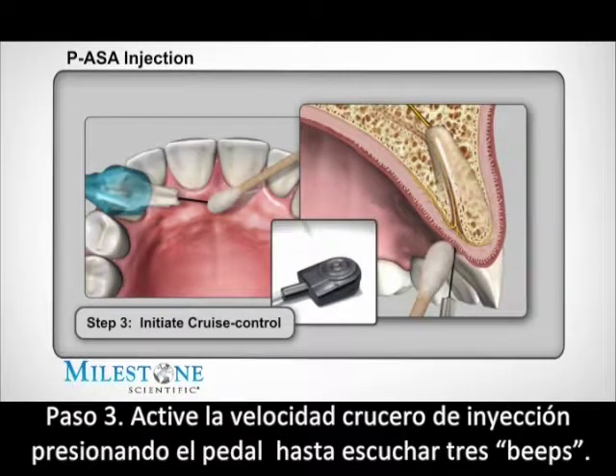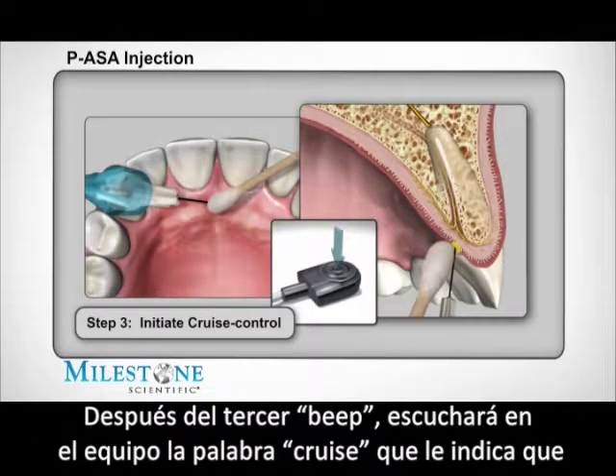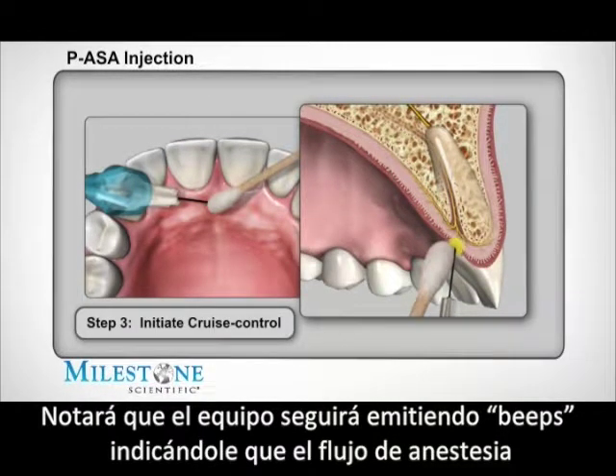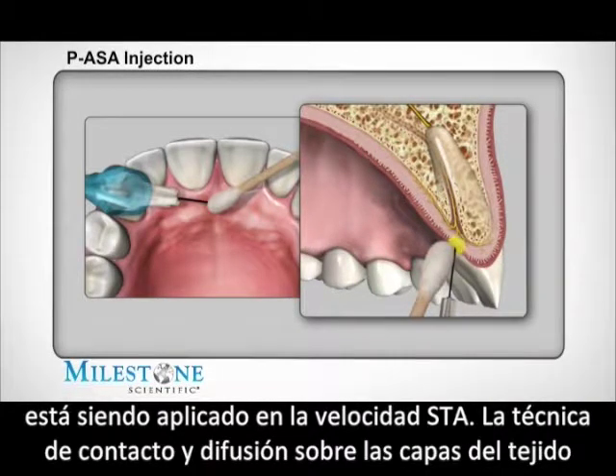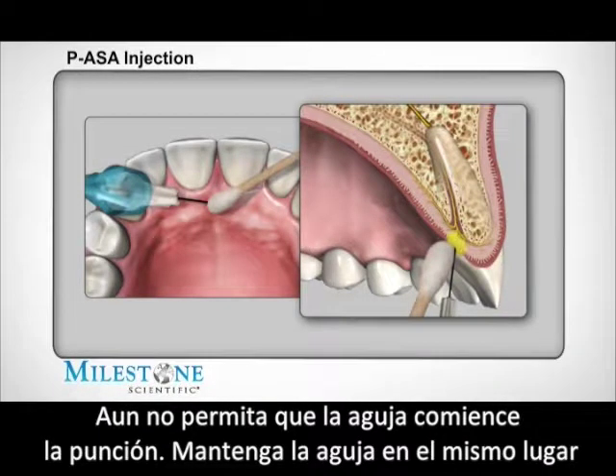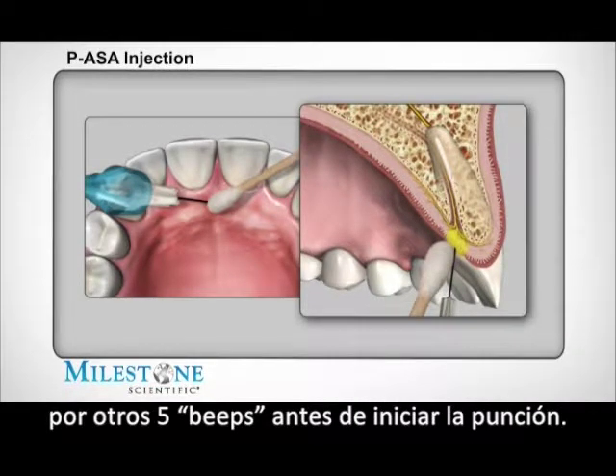Step 3: Initiate cruise control by depressing the foot pedal and counting three audible beeps. After the third beep, the STA system will announce the word 'cruise.' Upon hearing this, remove your foot from the foot control pedal. The STA system will continue to beep indicating anesthetic solution is continuing to flow. Allowing anesthetic to contact and diffuse through the outer layers of tissues will produce a topical anesthetic effect, numbing the surface. Do not allow the needle to puncture the tissue at this time. Continue to allow the needle to stay on the surface for another five beeps before initiating needle penetration.